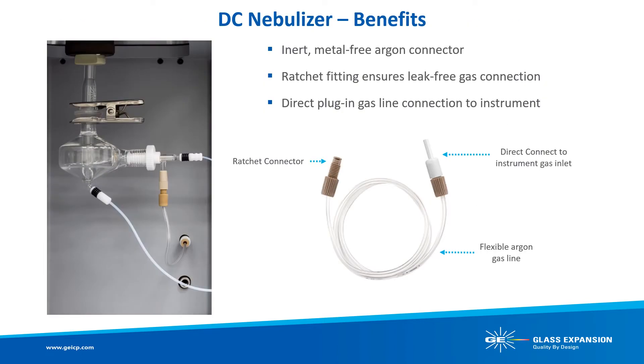The DC design provides a significant improvement to the nebulizer gas connection, helping to maintain optimum back pressure for consistent day-to-day performance. The reliable ratchet click-and-seal DC fitting ensures a leak-free gas connection by clicking or ratcheting when a proper seal is achieved and preventing overtightening. At the other end of the DC gas line is an ICP-specific quick connect to the argon gas supply. Here is an example of our DC Sea Spray nebulizer installed on the iCap Pro Duo, where the DC gas line replaces the original rigid gas line.